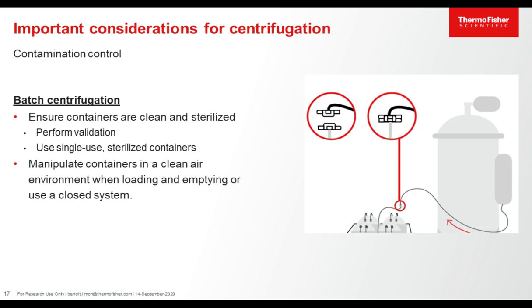To control contamination in a batch centrifuge, one should ensure that the containers are clean and sterilized by performing cleaning and decontamination validation, or by using single-use, sterilized, ready-to-use containers. The containers should be manipulated in a clean air environment when loading and emptying the solution, and the use of a closed system is also possible.